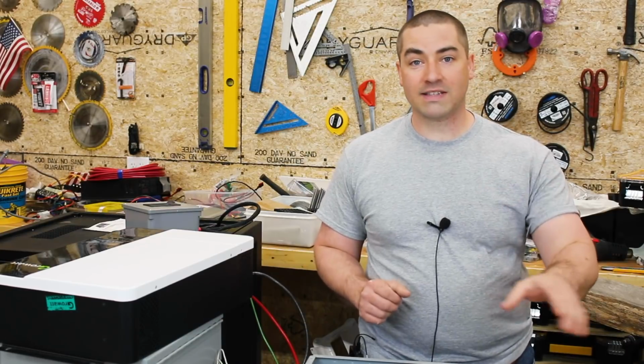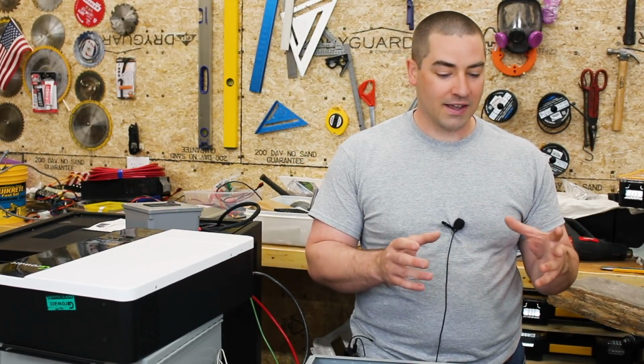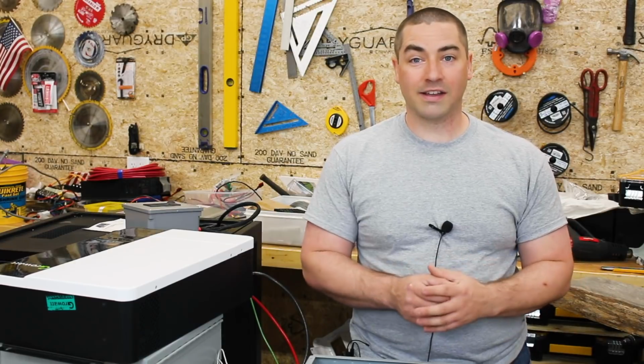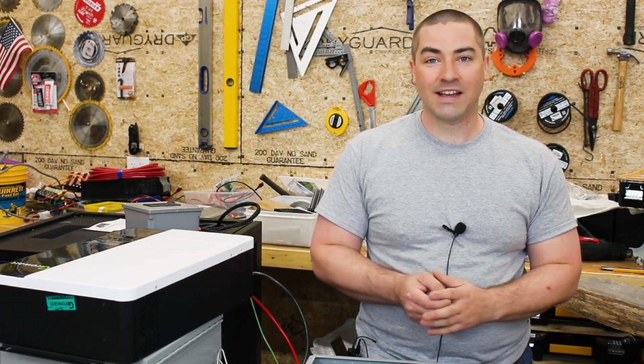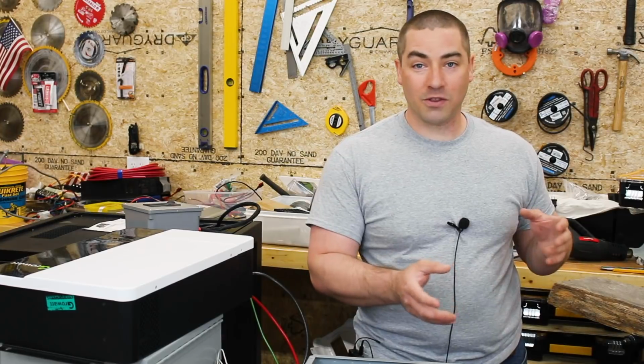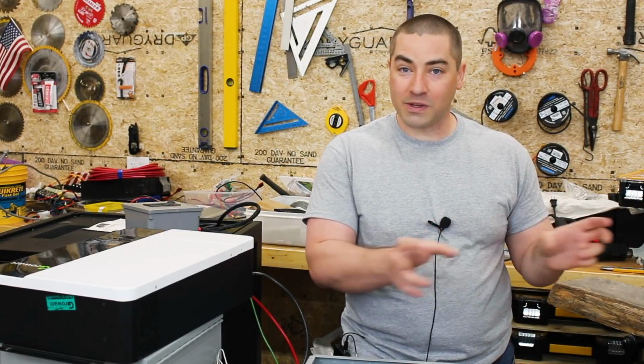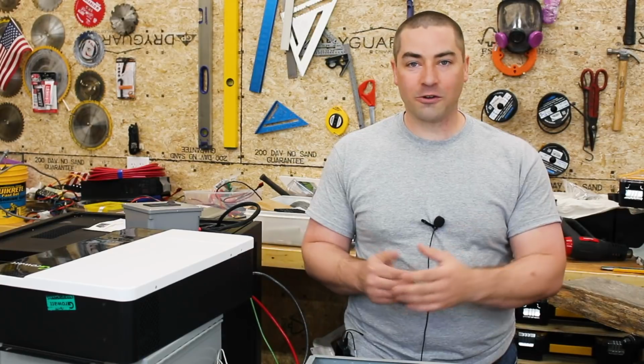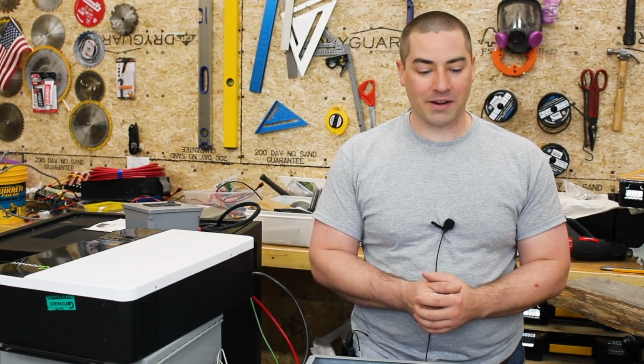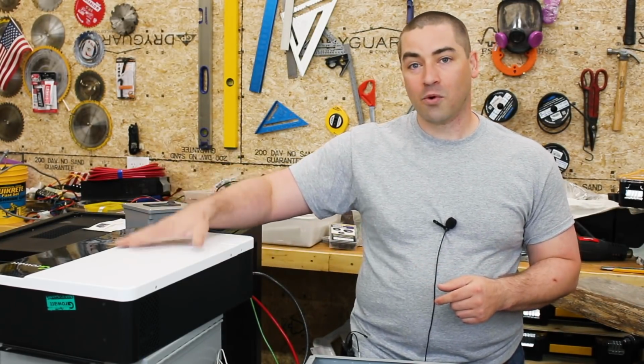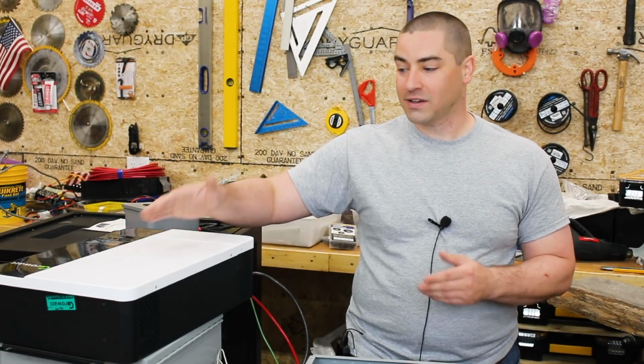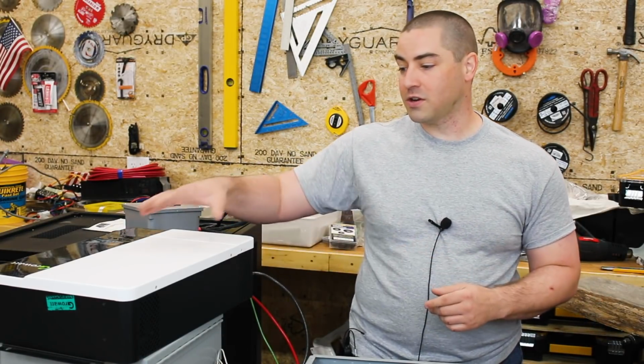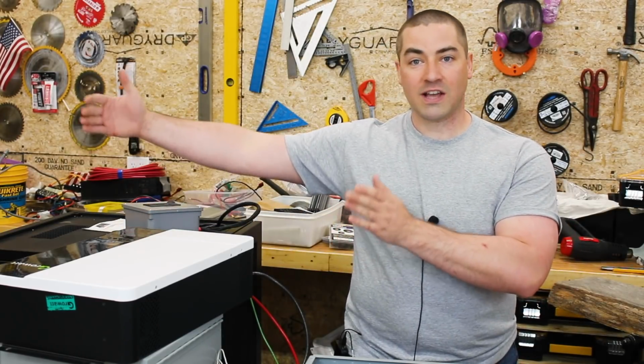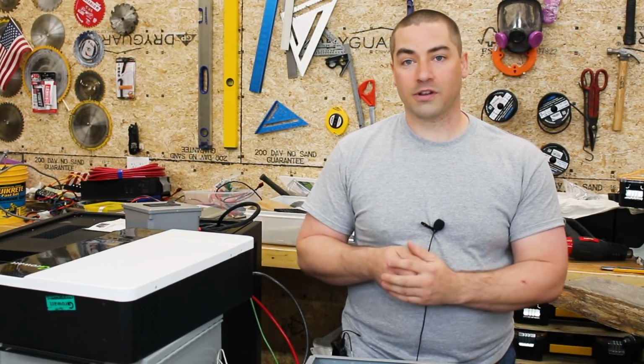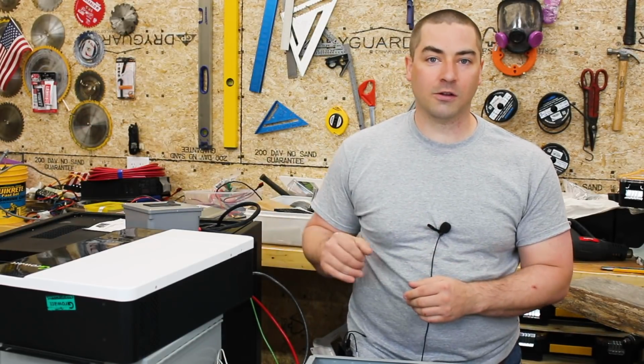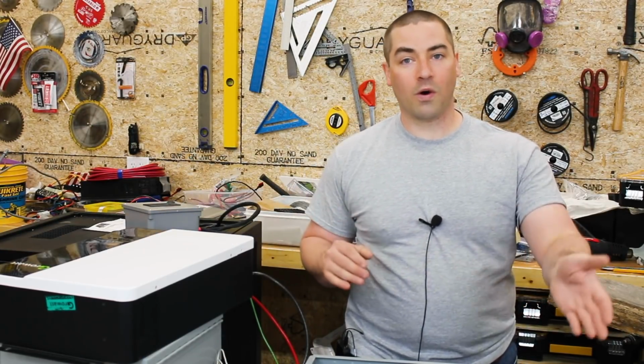Now I found it really exciting to see what the auto transformer could do. It's relatively small, even though it's very heavy for its size, and it really did great. When you split the load on 2 different phases, the auto transformer isn't even seeing anything going through it. This is why you can parallel more than one of the Growatt inverters to just one auto transformer. So you could have 2 Growatt inverters, 10,000 watts, with just one auto transformer. Or you could have 3 with 15 kilowatts of Growatt inverters with one auto transformer.